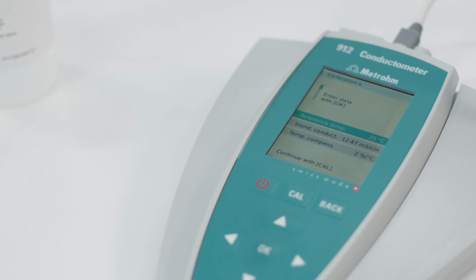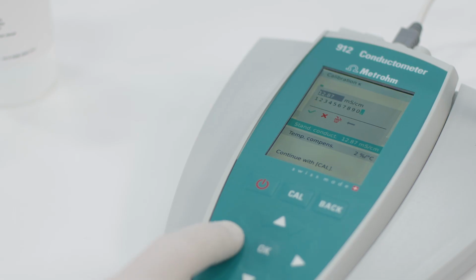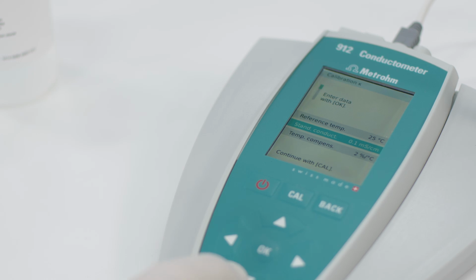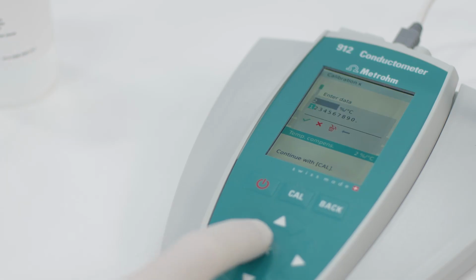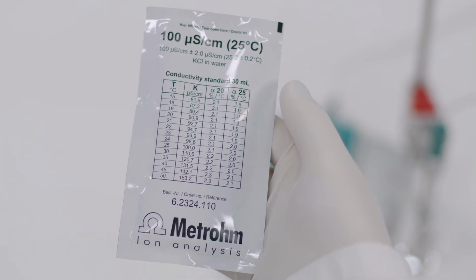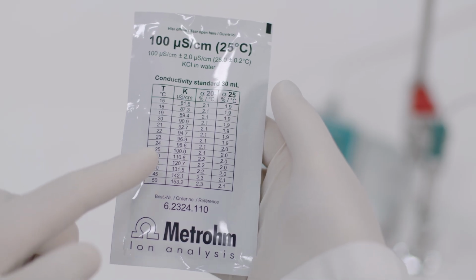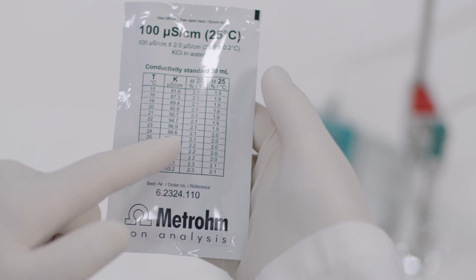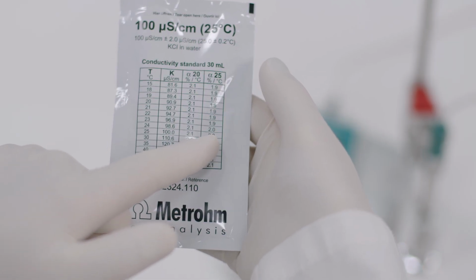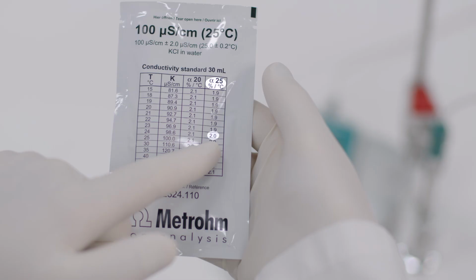Now you will need to enter the value of your conductivity standard. If you use standards from Metrohm, this value is either 0.1 millisiemens per centimeter or 12.87 millisiemens per centimeter. Ensure the temperature compensation settings are appropriate for your measurement needs. The correct value for the temperature compensation can be found on the sachet. As an example, if your lab is at 24 degrees Celsius and you want to reference it to 25 degrees Celsius, then choose the value 2% per degree Celsius.